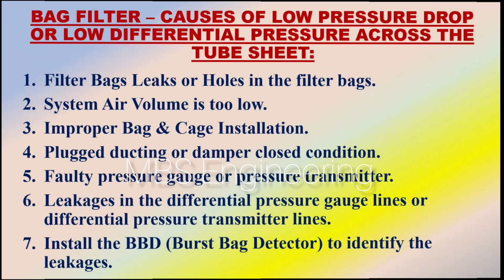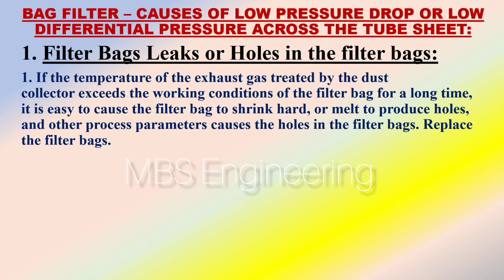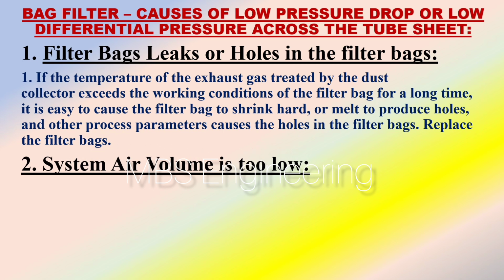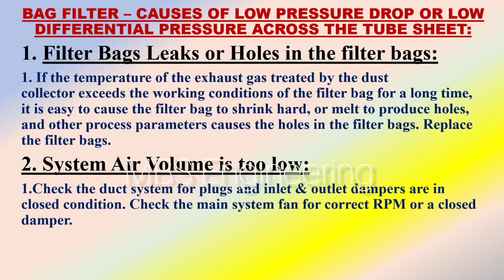One of the main causes of low differential pressure is the filter bags leaks or holes in the filter bags. Point number 1. If the temperature of the exhaust gas treated by the dust collector exceeds the working conditions of the filter bag for a long time, it is easy to cause the filter bag to shrink hard, or melt to produce holes, and other process parameters cause the holes in the filter bags. Replace the filter bags.